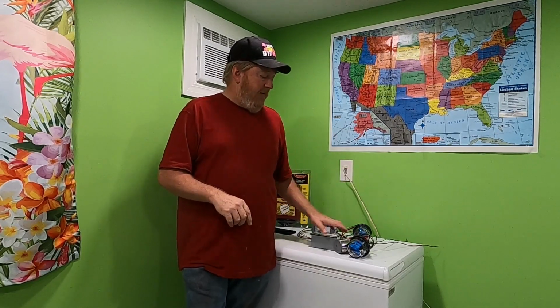Now, if you'd had a lightning arrestor or surge suppressor on that system, it would have clamped those two together and probably blown the main breaker before any damage happened to the house. If you didn't have one, your house probably caught on fire. So that's another type of surge you're going to see—squirrel, transformer, substation type thing.